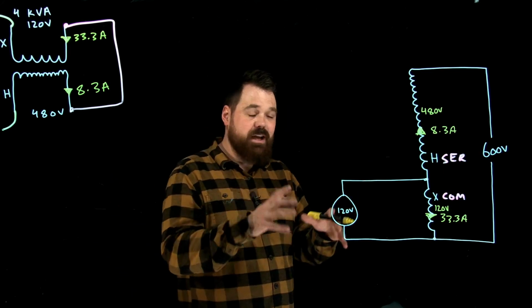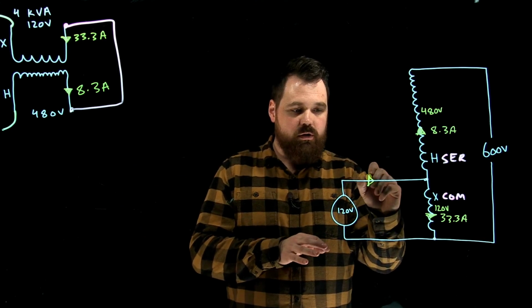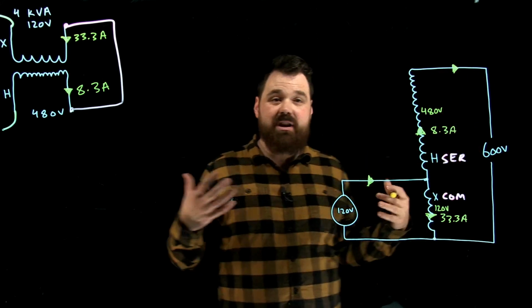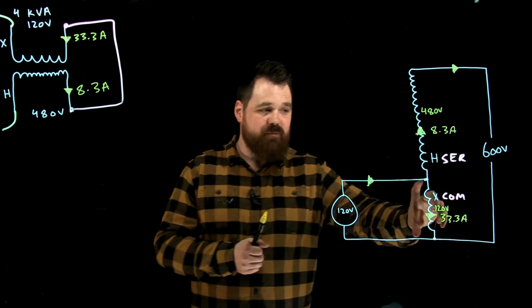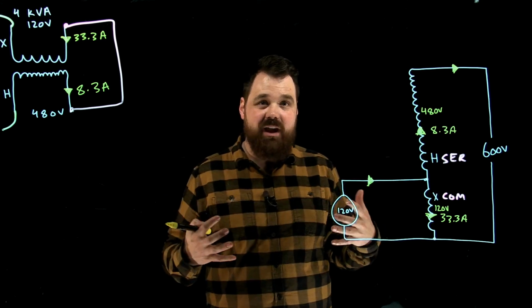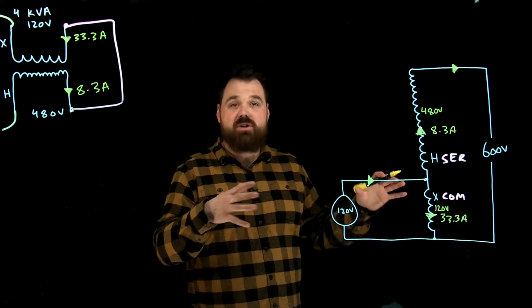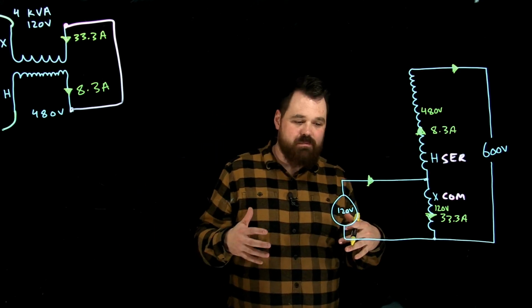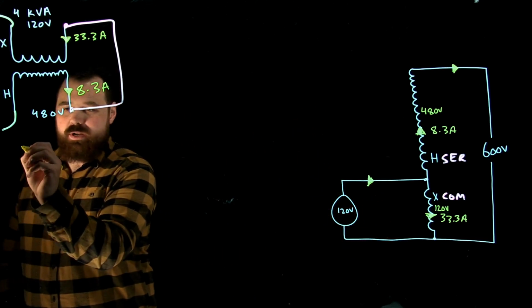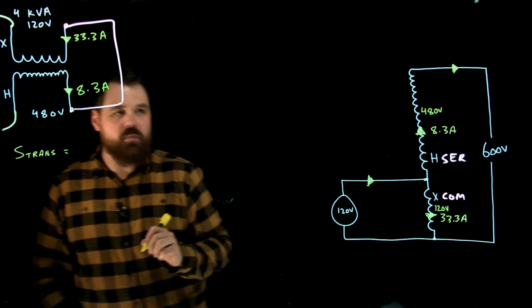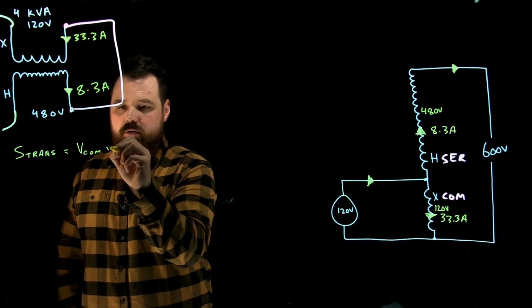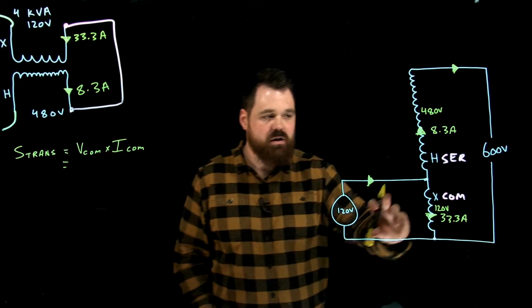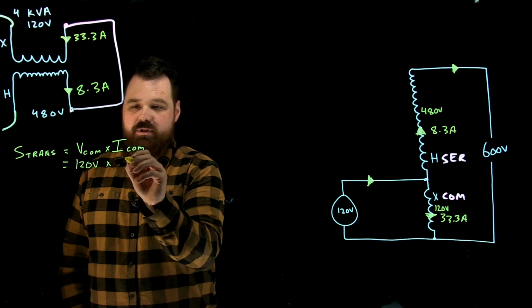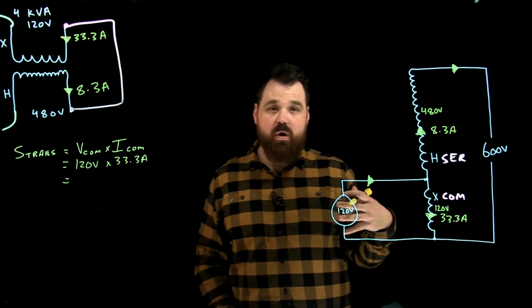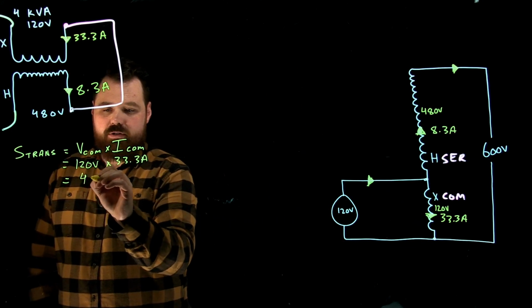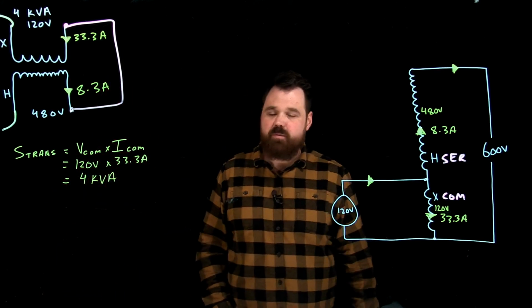Now, that's all really cool, that's fine and dandy, but now when it's an auto transformer, we want to know what my total ratings are. Well, we know in an auto transformer, I can take my transformed VA plus my conducted VA to get my total VA. I do have another video which discusses all of those in a little more detail. I'll link that up above as well as in the description below to get the basics. But we can figure out on this transformer, what is our S transformed? Well, remember, transformed VA is common voltage times common current. So in this case, 120 volts times 33.3 amps. So my transformed apparent power, which is just on this common winding, gives us around 4 kVA, depending on your decimal places, but it's close to 4 kVA.